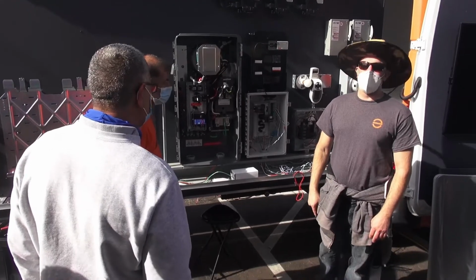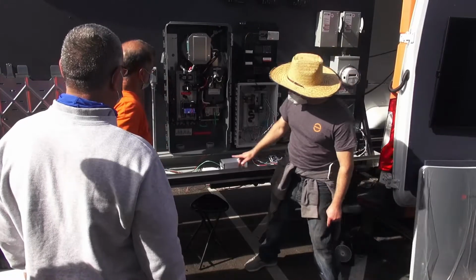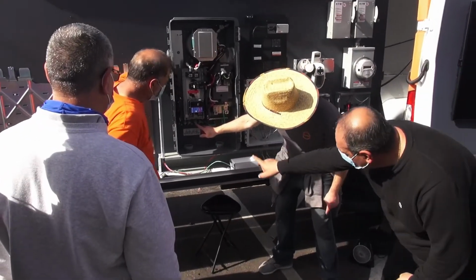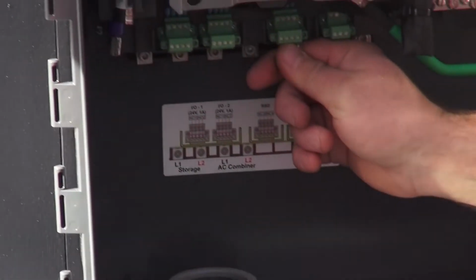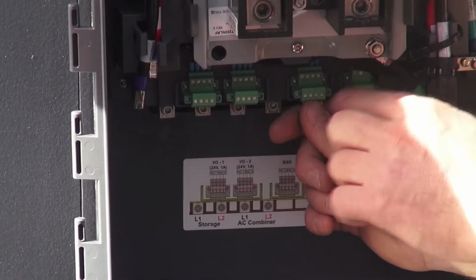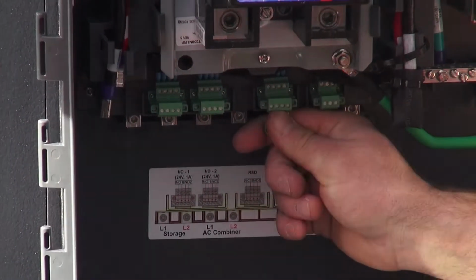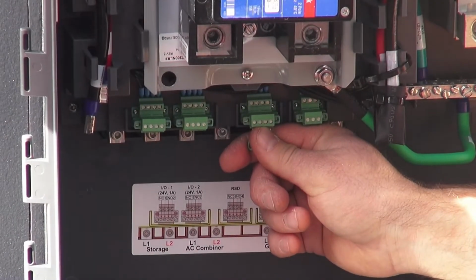And my hint to you is it's really hard to tell. Super hard. The easiest way to tell is that there's an additional port. Not the jumper, this port. Take it out. You see that? The other one goes this way, and this only. This is new. Yeah, that's 3 of them. Rapid shutdown disconnect switch.